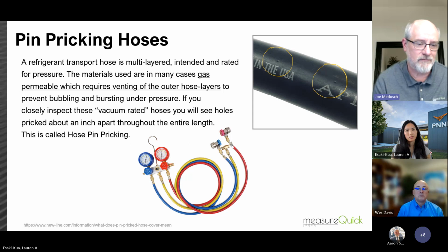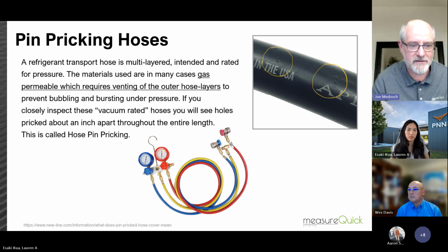But then when it's turned off, even with low loss fittings—which try to keep everything inside at the connection so it doesn't just bleed out when you open the tube—it's still allowing a lot to escape. By the next day, most of that refrigerant did not stay in there, and if it's much longer, it works its way out of the hoses entirely. So we're not keeping stuff inside the hoses.